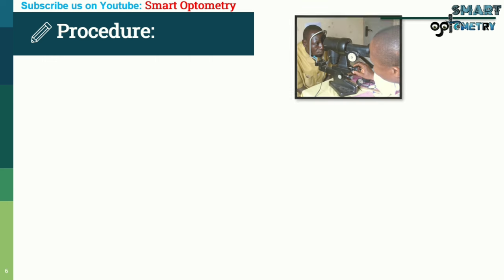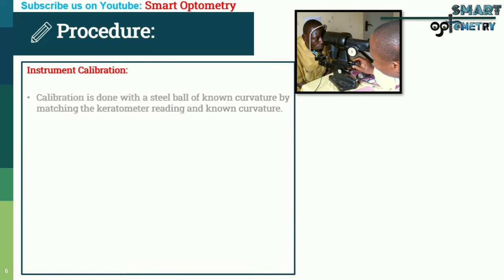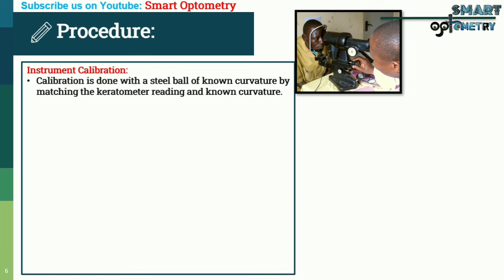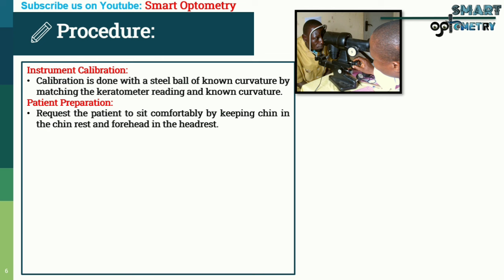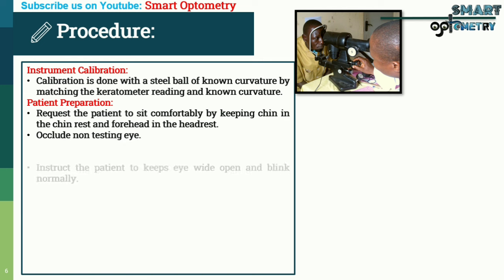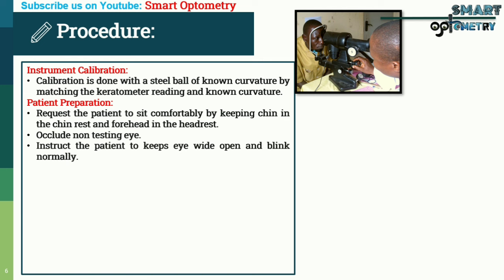Procedure of keratometer. Calibration: calibration is done with a steel ball of known curvature by matching the keratometer reading to the known curvature. Patient preparation: request the patient to sit comfortably with chin in the chin rest and forehead in the headrest. Occlude the non-testing eye and instruct the patient to keep the eye open and blink normally.